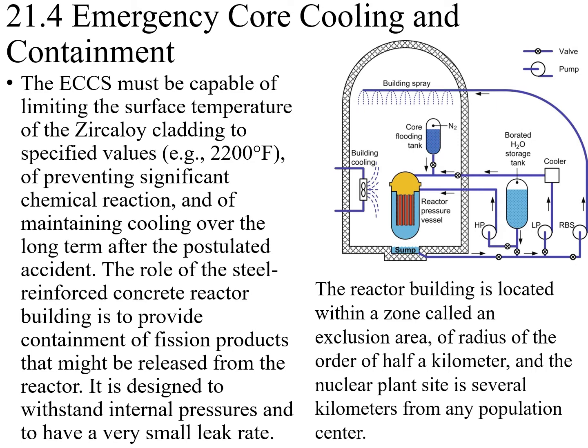The role of the steel reinforced concrete reactor building, or this containment building, is to provide containment of fission products that may be released from the reactor. It is designed to withstand the internal pressure and to have a very small leak rate. In addition, the reactor building is located within a zone called an exclusion area of a radius of the order of half a kilometer, and the nuclear plant site is several kilometers from any population center.